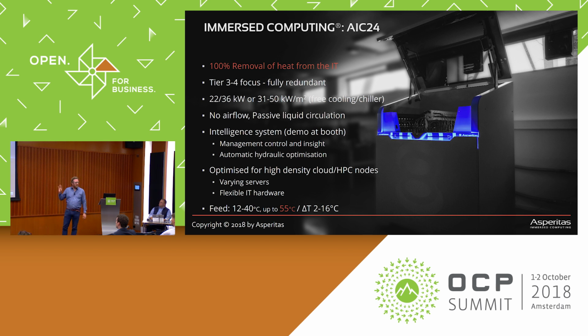The system has been developed for a tier 3 to 4 level data center environment, built for redundancy, resiliency, and high quality operation. It can facilitate 22 to 36 kilowatts inside each module. It's modular, so you can stack them to make a larger environment, translating to approximately 31 to 50 kilowatts per square meter.